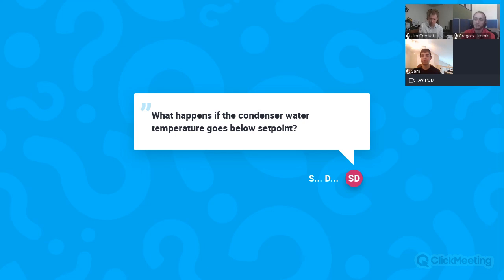That's why we would even say give yourself a buffer so you don't go right up to that manufacturer limit. Give yourself a couple degrees to allow for those extenuating circumstances when it is really cold outside. Maybe you're just flowing water over the towers with the fans off, and it still gets too cold. Then you've done all you can at that point. So then you may be forced to lower your chilled water temperature.